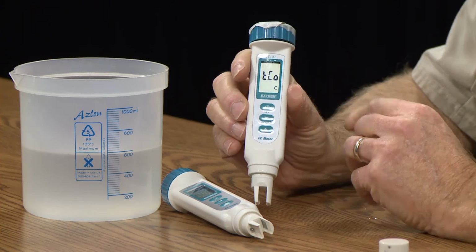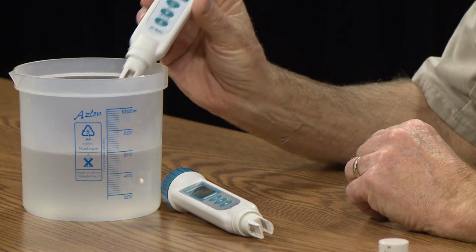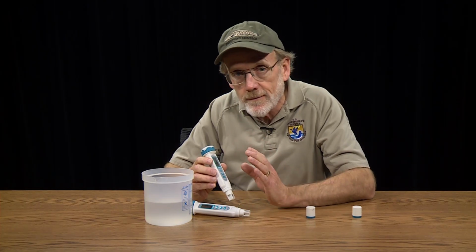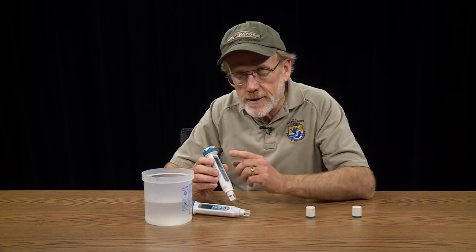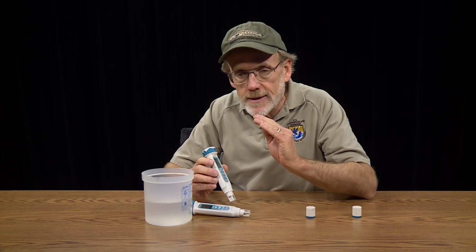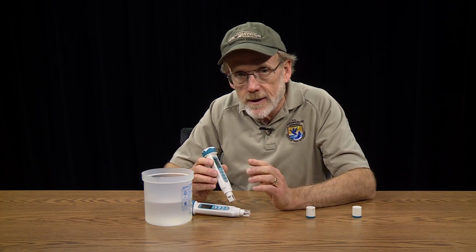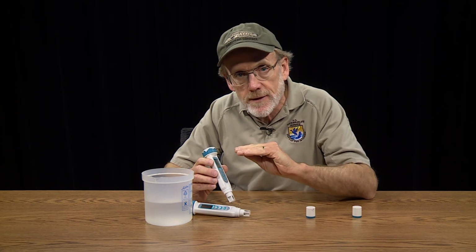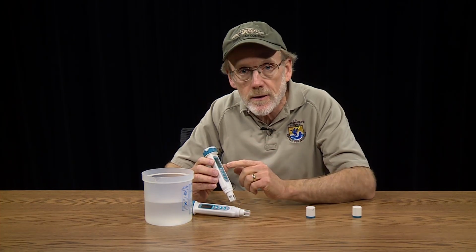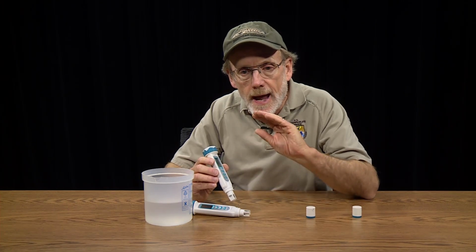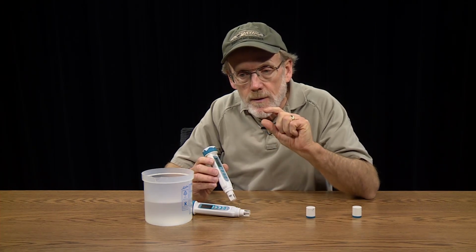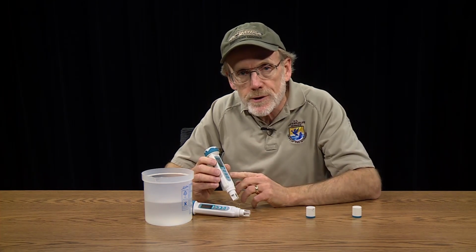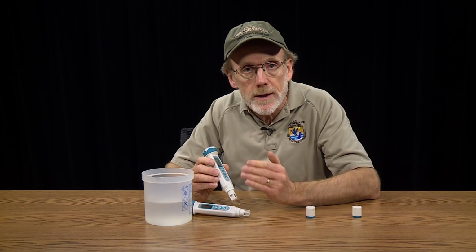So how these machines work is that when you take a water conductivity reading, think of it this way, it takes a reading, but it doesn't display it, and then it takes a temperature reading, and it calculates the difference between the water temperature and the specific temperature you set. In this case here is 25 degrees, and adjusts the original conductivity reading by that percent per degree difference.